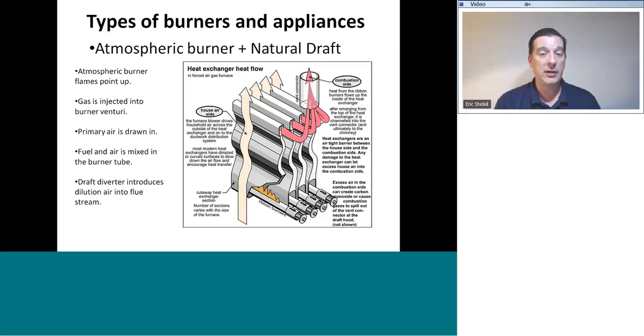So if you're looking at a water heater on a warm day in the summertime and the burner fires, it won't draft very well at first. It takes a while for things to warm up, for that draft to really get going, and for that suction to actually occur. But it does. So that's important to know. We can measure draft, and we'll look at that in a little bit.